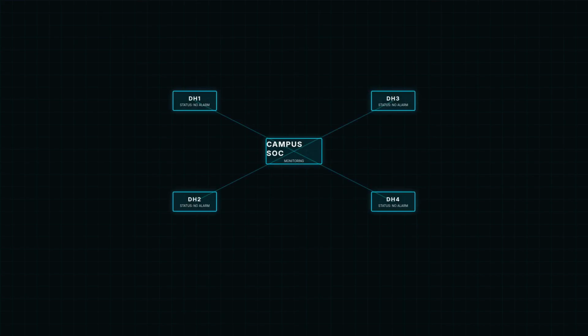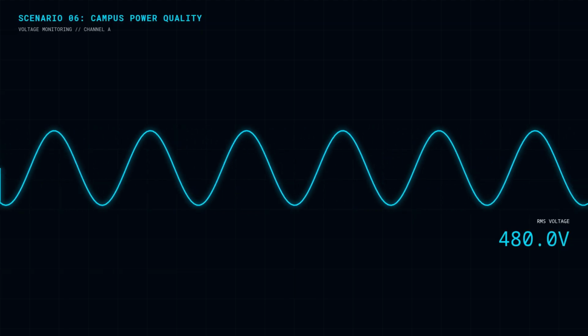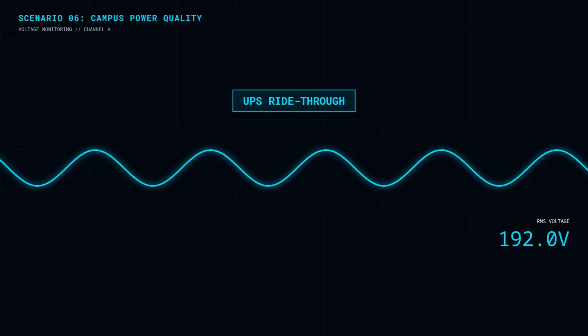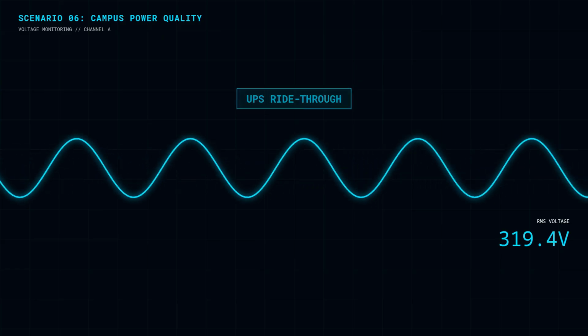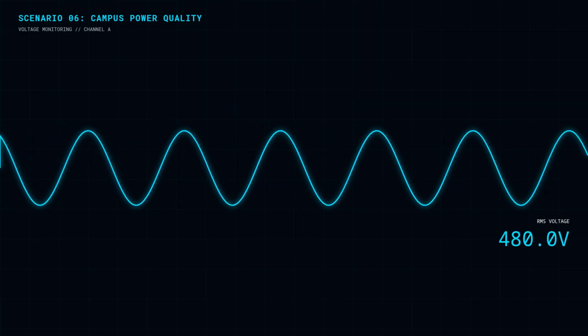Scenario 5. VESDA pre-alarm. Trigger in DH2. Verify the alarm routes to the campus SOC and does not propagate to local panels in other halls. Scenario 6. Campus power quality event. Inject a 3-second voltage sag. We verify that all UPS systems ride through without transferring to battery.